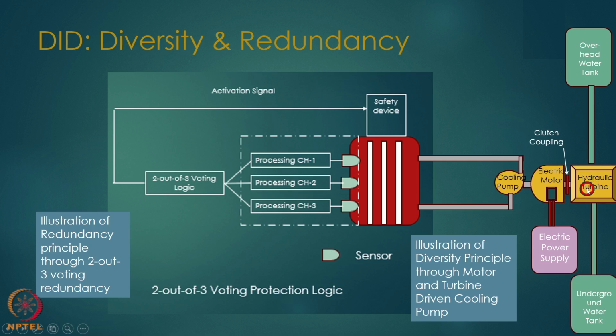So here the turbine will be ensuring the operation of the pump, and if the motor is not available, vice versa also. If the turbine is not available, then the electric motor can. So we have a redundant system, turbine and motor, operating on diversified principles. One is by power water, for which you don't require any electricity. Water will enter and operate this. For the long term scenario, we have to work out certain things, so we will not go into that now, but those provisions also exist.